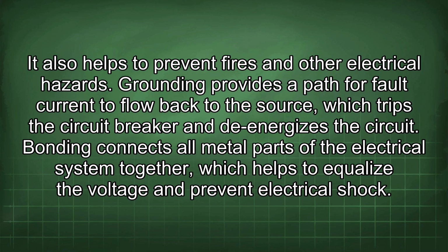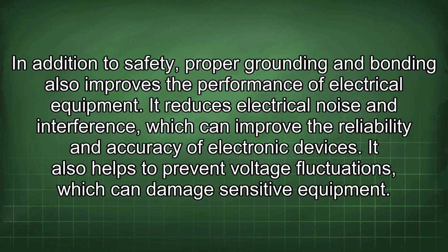Grounding provides a path for fault current to flow back to the source, which trips the circuit breaker and de-energizes the circuit. Bonding connects all metal parts of the electrical system together, which helps to equalize the voltage and prevent electrical shock. In addition to safety, proper grounding and bonding also improves the performance of electrical equipment.